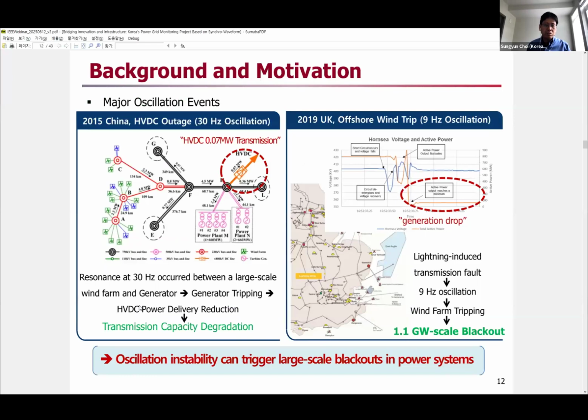In a major oscillation event in 2015 in China, there was an interaction between wind turbines and the conventional generation systems, generating 30 hertz oscillations. Because of these oscillations, the generators on this side tripped. Therefore, the long power delivery through this HVDC, high voltage DC transmission, was reduced. And in 2019 in the UK, a lightning induced transmission fault generated 9 hertz oscillations with a wind farm trip, eventually leading to a 1.1 gigawatt blackout. So all in all, oscillation instability can trigger large-scale blackouts in recent power systems.